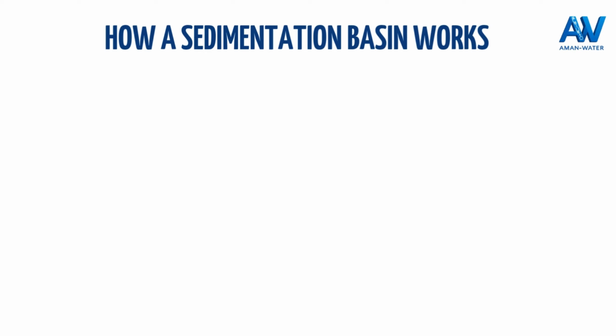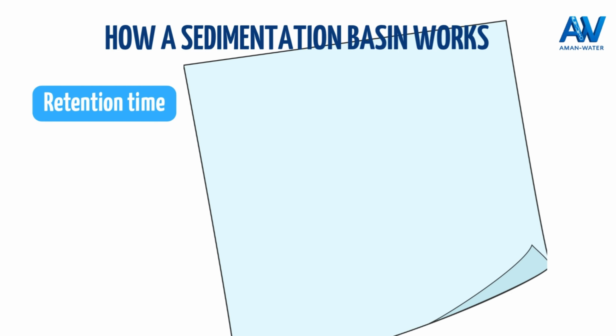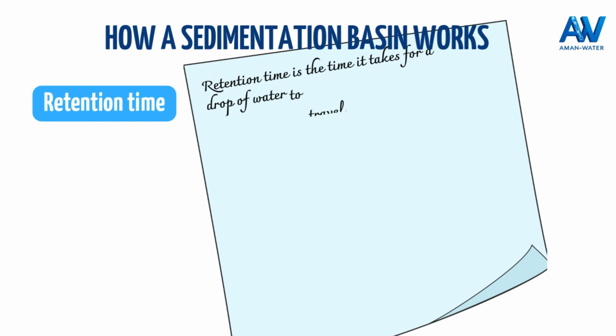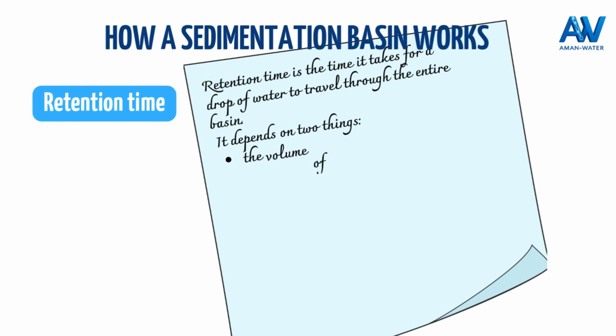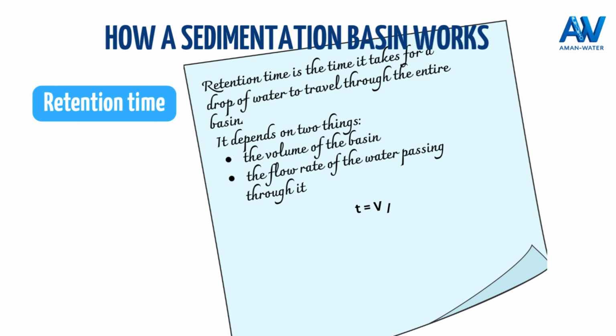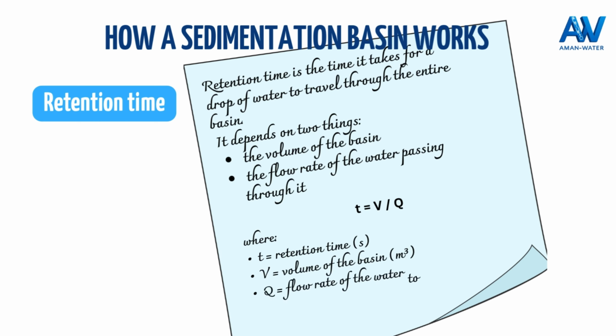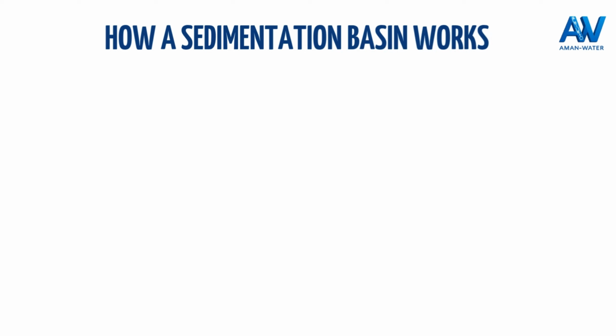Now, one question always comes up: how long should the water stay in the tank to be properly clarified? That's where an essential concept appears: retention time. It's the time it takes a drop of water to travel through the whole tank. It depends on two things: the volume of the tank and the flow rate of the water passing through it. So if I know the flow rate and I want the water to stay for 3 hours, I can calculate the volume I need. But that's not all.